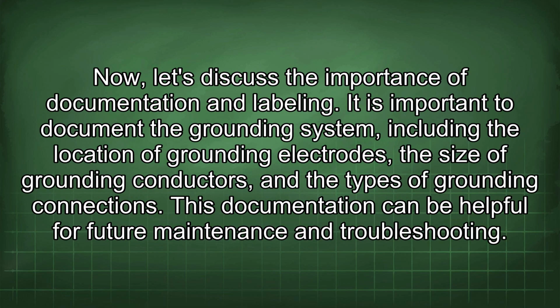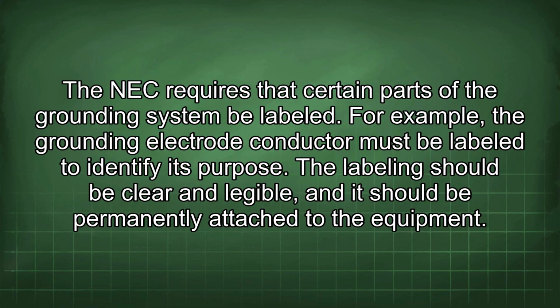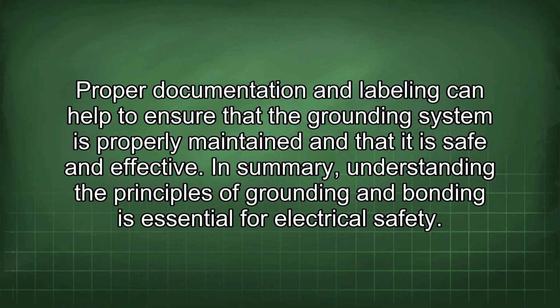Now let's discuss the importance of documentation and labeling. It is important to document the grounding system, including the location of grounding electrodes, the size of grounding conductors, and the types of grounding connections. This documentation can be helpful for future maintenance and troubleshooting. The NEC requires that certain parts of the grounding system be labeled. For example, the grounding electrode conductor must be labeled to identify its purpose. The labeling should be clear and legible, and it should be permanently attached to the equipment.